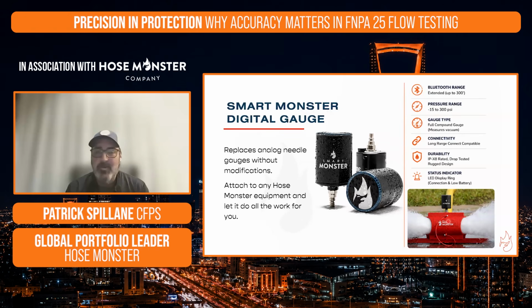It can be adapted to any of our products. The way that works, it's a wireless charging battery that powers our device, and it sends out a Bluetooth signal, with Bluetooth range up to 300 feet. So we get quite a far distance there. It's a full compound gauge, from negative 15 to 300 PSI. So again, this is why we can use it on either side of the fire pump at the same time.